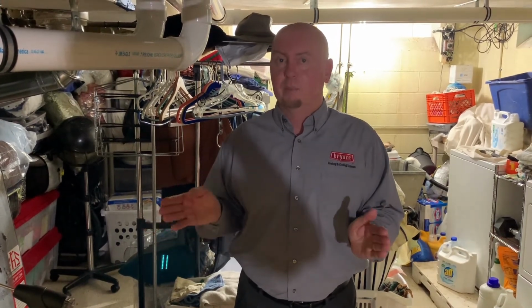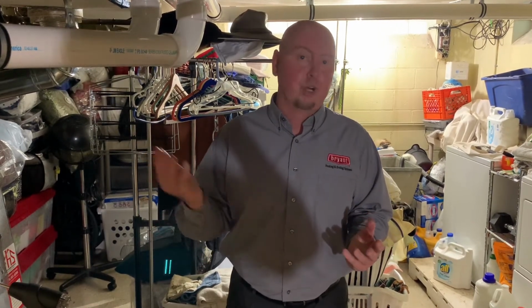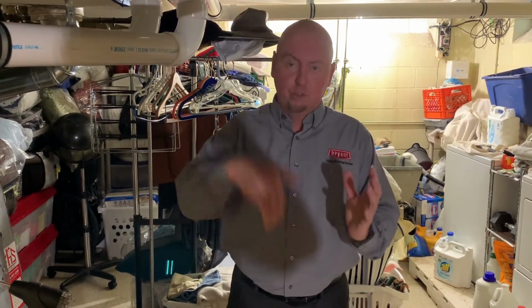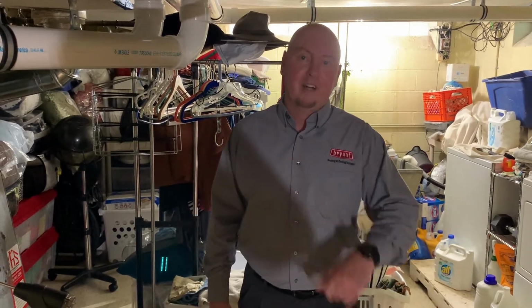If that number goes up when the blower comes on, that could indicate something wrong with the primary heat exchanger, a crack, because when the blower comes on, it's pushing air in, and it goes out through the flue pipe, raising the O2 level. Hope you find that helpful.